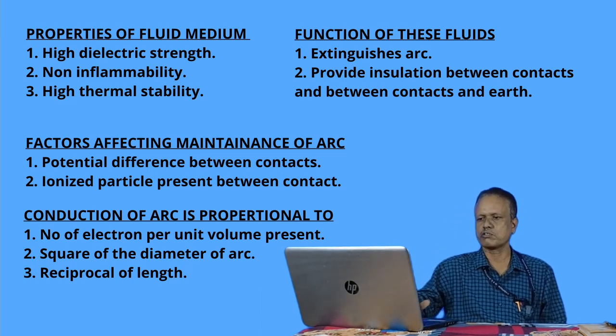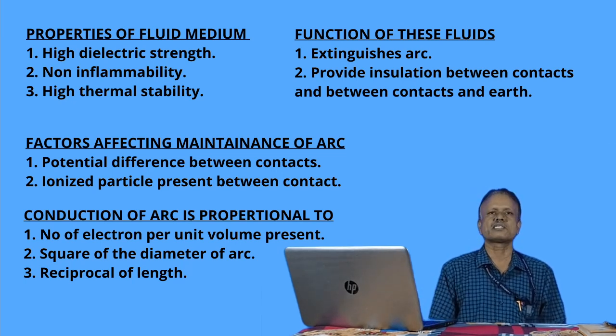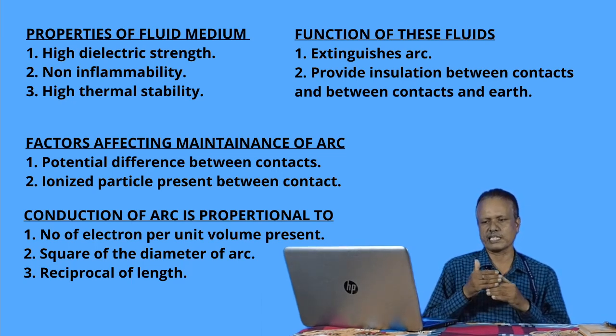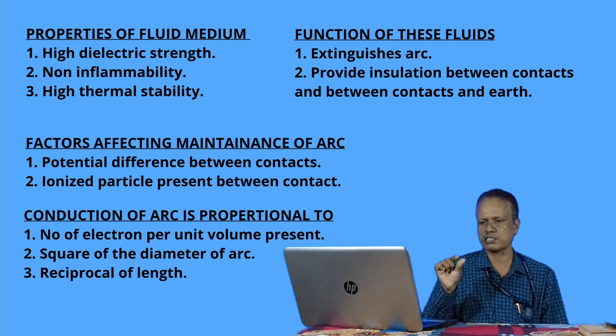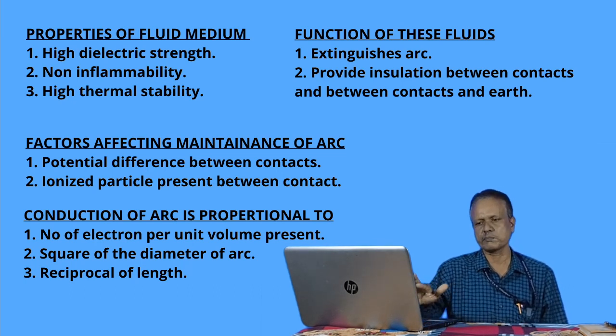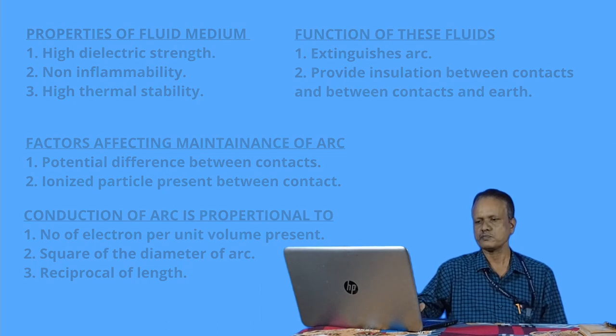Thereafter we go to the conduction of the arc, which is proportional to 3 things: the number of electrons per unit volume present, the square of the diameter of the arc, and the reciprocal of the length. The reciprocal of the length is the major factor, and we cannot increase the length due to the high voltage circuit breaker. Similarly, if we increase the square of the diameter of the arc, then the arc will persist. Similarly, if the number of electrons per unit volume is more, then also the arc will persist. So these are the 3 factors on which conduction of the arc depends.